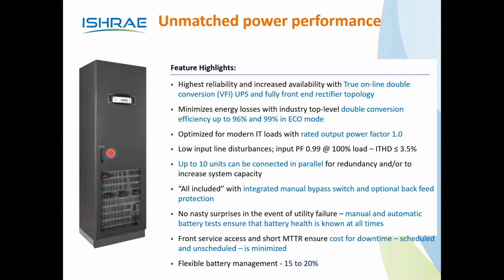The customer replaces the entire battery bank instead of only 3 or 4 batteries, because earlier it was a fixed battery management topology. The system works with 40 blocks only. We cannot remove 4 or 5 batteries from there. If we remove 4 or 5 batteries, the DC voltage required by the inverter will not be met. So that is mandatory. Here, flexible battery management gives a wide window, wide options. So in that case, it will, one sec.